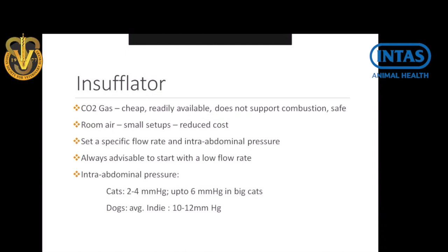Coming to the insufflator. For laparoscopy, we need to introduce a gas into the abdomen to make it distend. The best gas that you can use is carbon dioxide because it is cheap and readily available. It does not support combustion, so it's generally safe. There has been talk about using room air, which can supplement if you do not have medical grade carbon dioxide. It can be used initially in small setups because of its reduced cost, but medical grade carbon dioxide is also easily procurable, so that would be preferable.